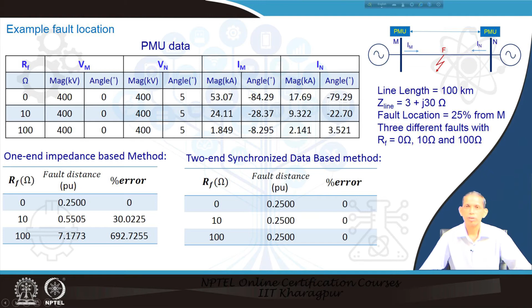So, we got the per unit distance to be 0.25 for 0 fault resistance, but with increase in fault resistance the impedance based approach gives us erroneous fault distance. But with 2 end synchronous data, using the formula from the last slide, in all the cases we are getting 0.25, because the fault voltage VF does not influence the accuracy. So, this is the strength of synchronous data being used for fault location application also.